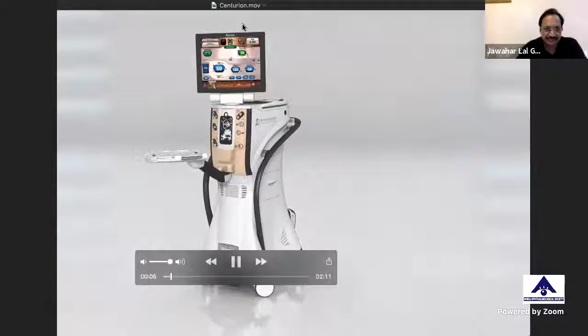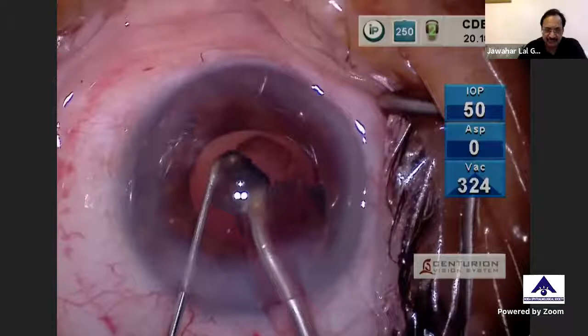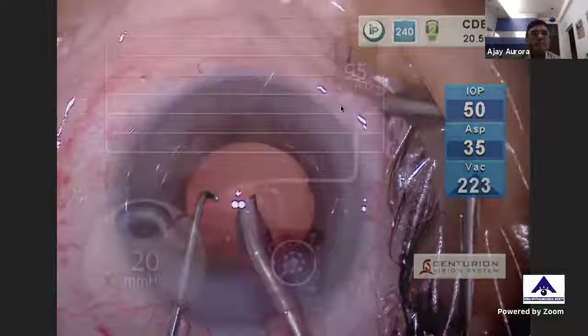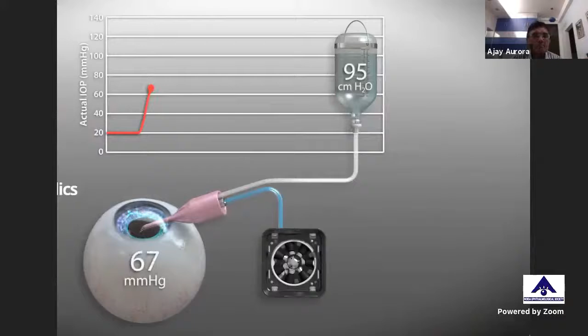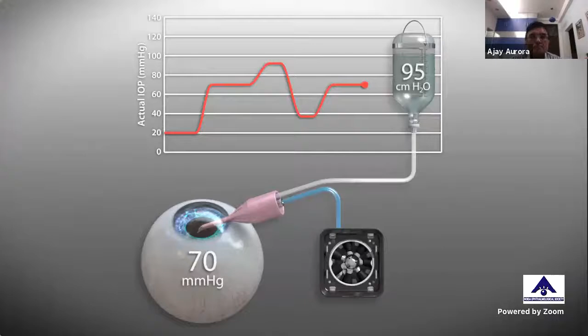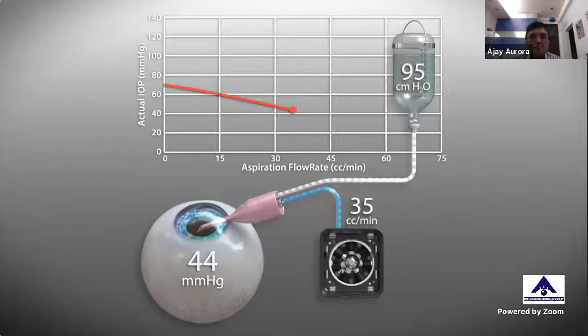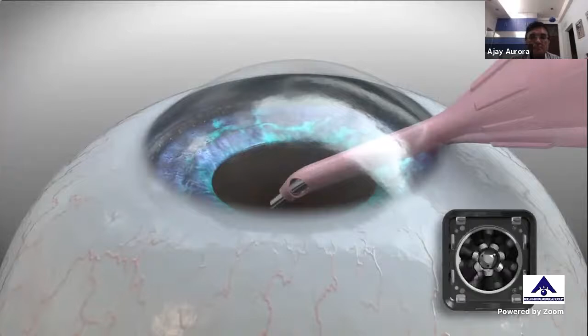During cataract removal, surgeons are managing irrigation, aspiration, and energy to emulsify and remove the lens. When irrigation is initiated, the eye will reach an IOP equivalent to the bottle height. For example, a bottle height of 95 centimeters of water creates 70 millimeters of mercury pressure. Different bottle heights result in different IOP levels. When aspiration flow occurs, the fluid movement results in a loss of pressure in the eye. Surgeons see this as a shallowing of the chamber and perhaps movement of the posterior capsule moving forward. With gravity and pressurized fluidics, the higher the aspiration flow, the more pronounced the shallowing of the anterior chamber.